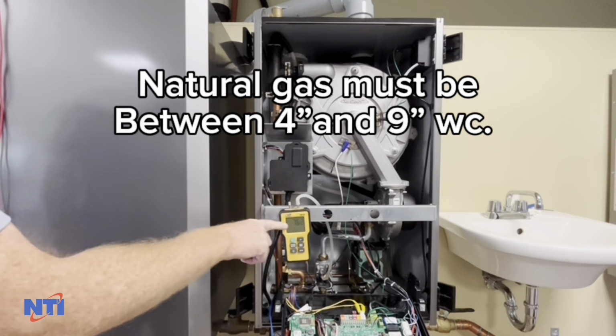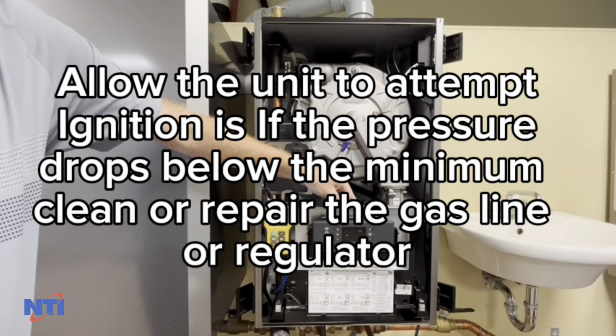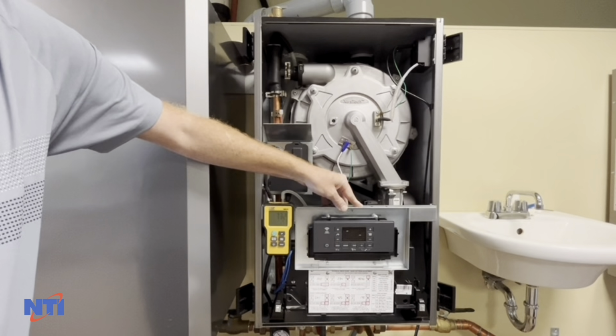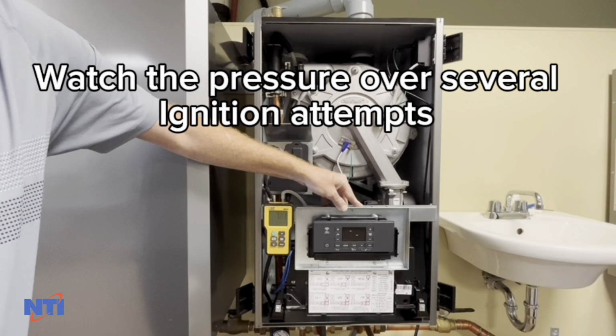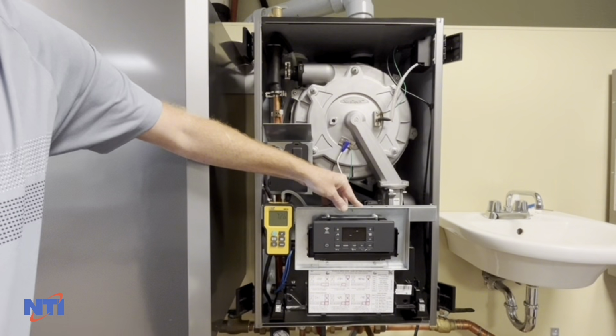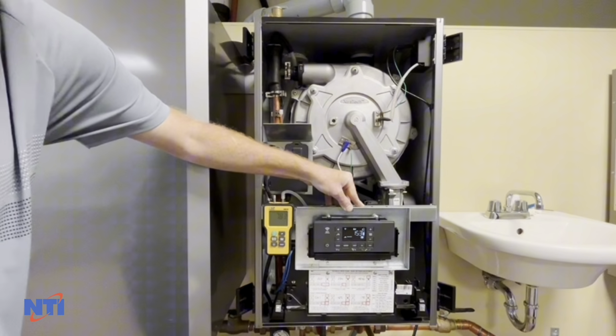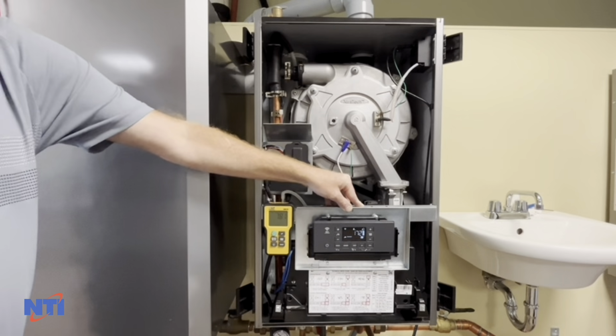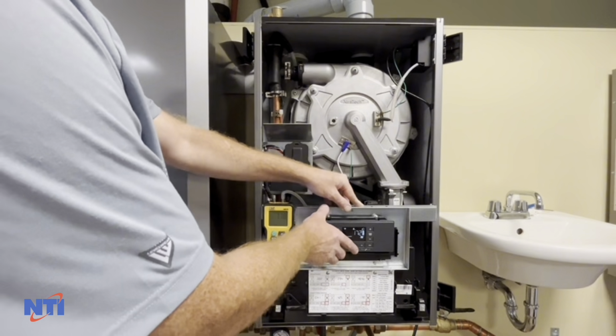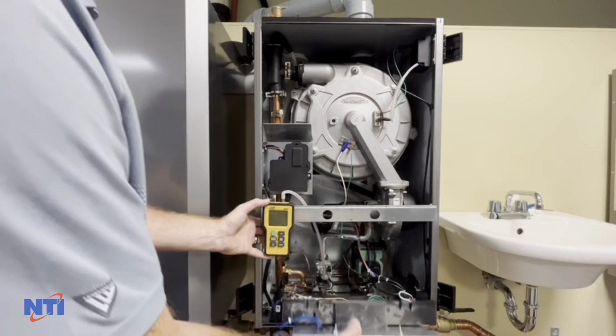If the pressure does not meet these specifications, inspect the gas line feeding the boiler. Make any repairs as needed. Allow the boiler to attempt ignition several times. Typical gas pressure drops are in the range of 1 to 2 inches. Excessive gas pressure drops indicate a problem with the gas line or gas regulator feeding the boiler.